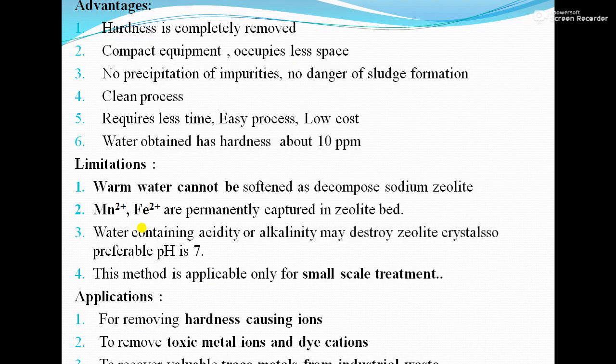Advantages of the zeolite process: first, hardness is completely removed; second, compact equipment occupies less space; third, no precipitation of impurities; fourth, no danger of sludge formation; fifth, it is a clean, easy, and low-cost process. Residual hardness of treated water is about 10 ppm.